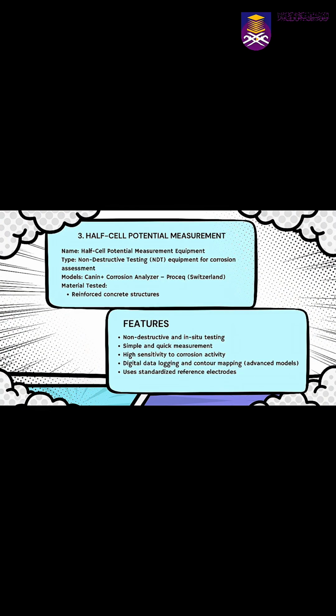Half cell potential measurement is a non-destructive testing, NDT, equipment for corrosion assessment. The model that is used is the Canin+ Corrosion Analyzer from Proceq Switzerland, and the material that is tested is reinforced concrete structure. Some of the features of this equipment are: it is non-destructive and in situ testing, simple and quick measurement, high sensitivity to corrosion activities, digital data logging and contour mapping, and it uses standardized reference electrodes.